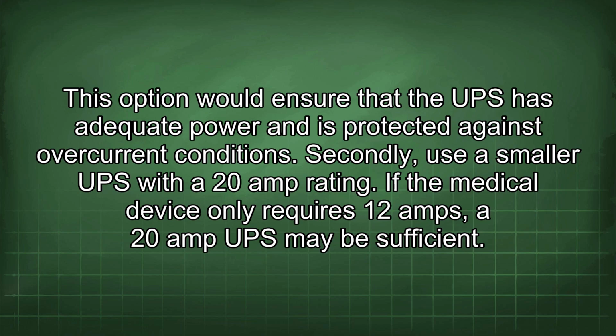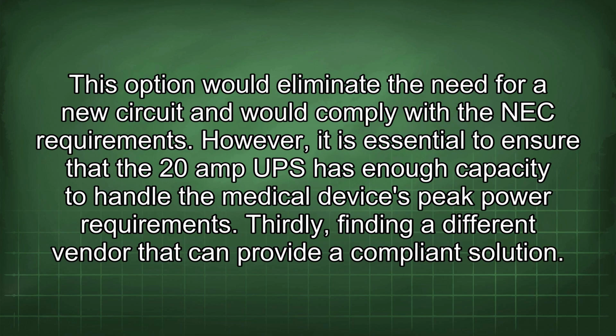Secondly, use a smaller UPS with a 20 amp rating. If the medical device only requires 12 amps, a 20 amp UPS may be sufficient. This option would eliminate the need for a new circuit and would comply with the NEC requirement. However, it is essential to ensure that the 20 amp UPS has enough capacity to handle the medical device's peak power requirements. Thirdly, finding a different vendor that can provide a compliant solution.